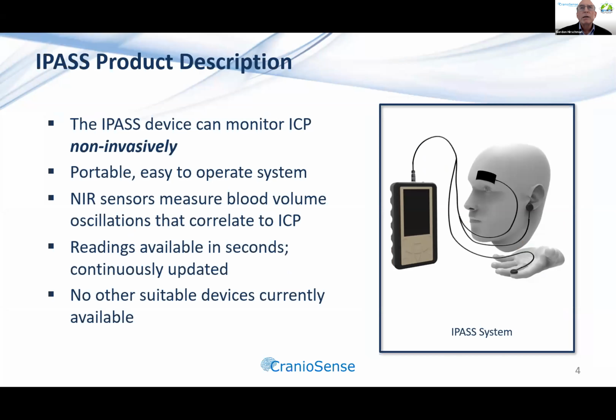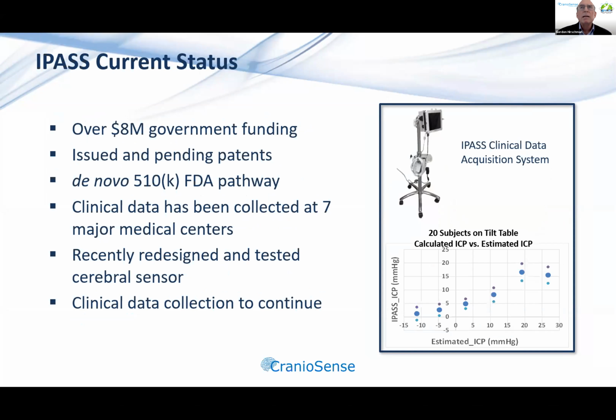The sensors use near-infrared light to measure blood volume oscillations, both inside and outside of the brain, with changes correlated to ICP levels. This assessment can be done rapidly and repeatedly for continuous monitoring. And IPASS provides a capability that is not currently clinically available. The IPASS technology has been developed with over $8 million in government funding, and there are both issued and pending patents. A pre-submission meeting with the FDA has confirmed the de novo 510K pathway to market.